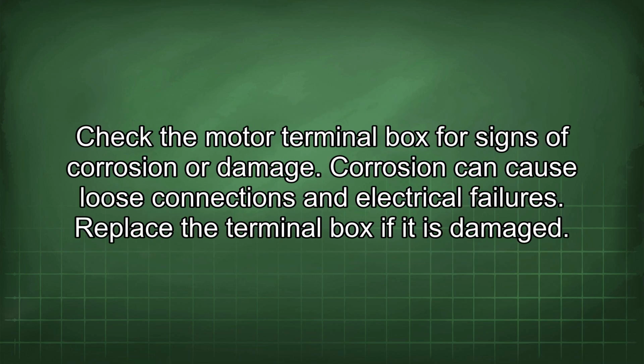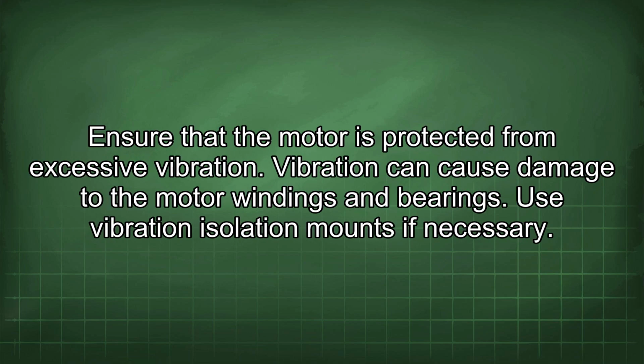Check the motor terminal box for signs of corrosion or damage. Corrosion can cause loose connections and electrical failures. Replace the terminal box if it is damaged. Ensure that the motor is protected from excessive vibration. Vibration can cause damage to the motor windings and bearings. Use vibration isolation mounts if necessary.